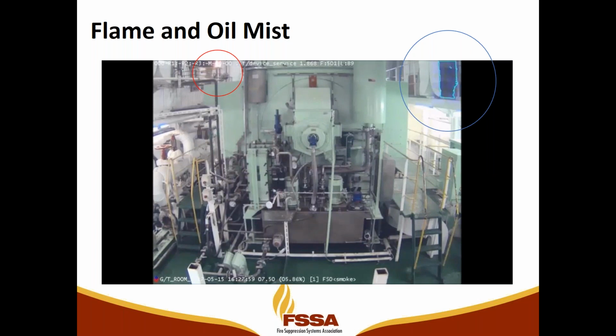So this is an actual event on a ship. There was an oil mist leak on an upper deck. On the right-hand side, you can see the oil mist being detected. On the left-hand side, you can see that there was a flame also on the other side of the engine. The crew in the engine control room received an alarm with a video pop-up of the event. They quickly analyzed the situation, activated the local application water mist system, knocked down the oil mist, and the fire was actually put out with a fire extinguisher.